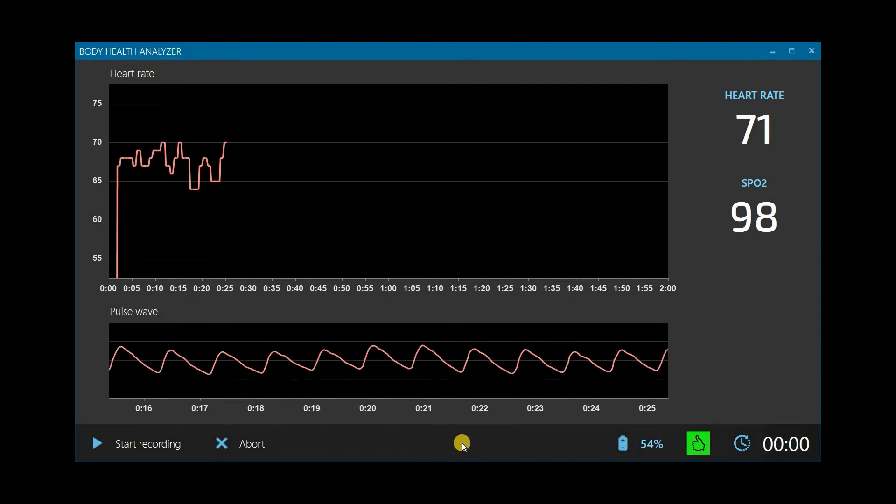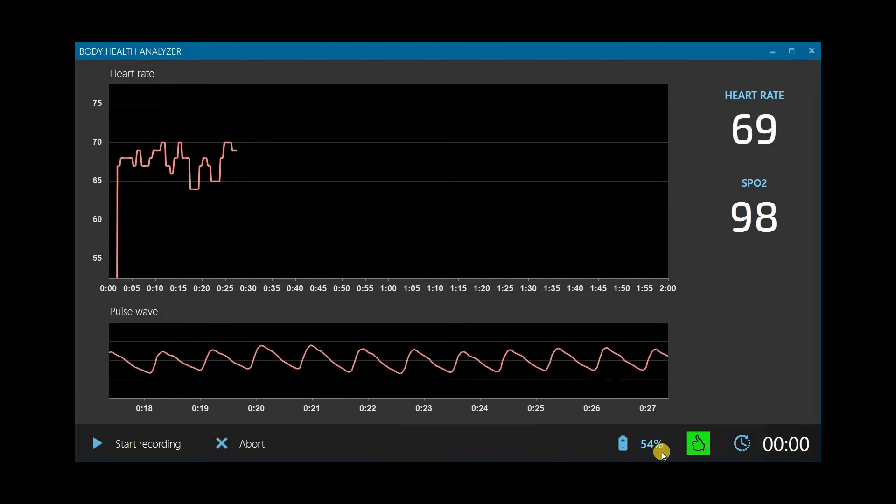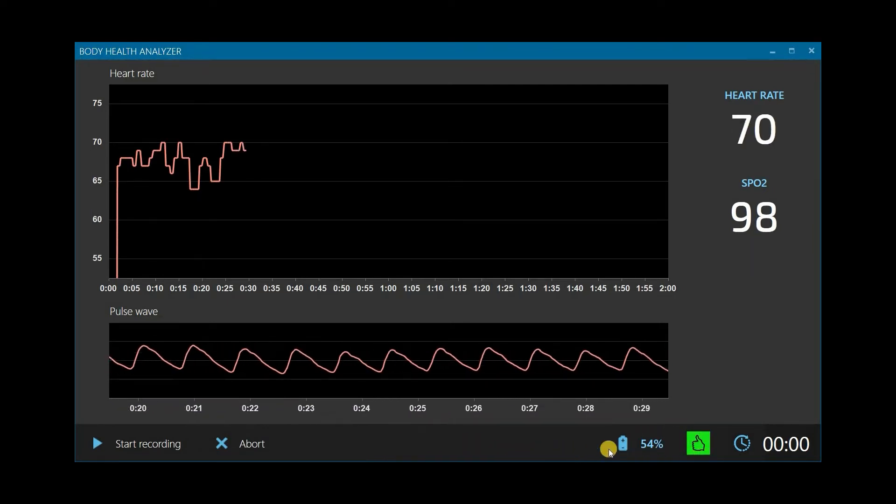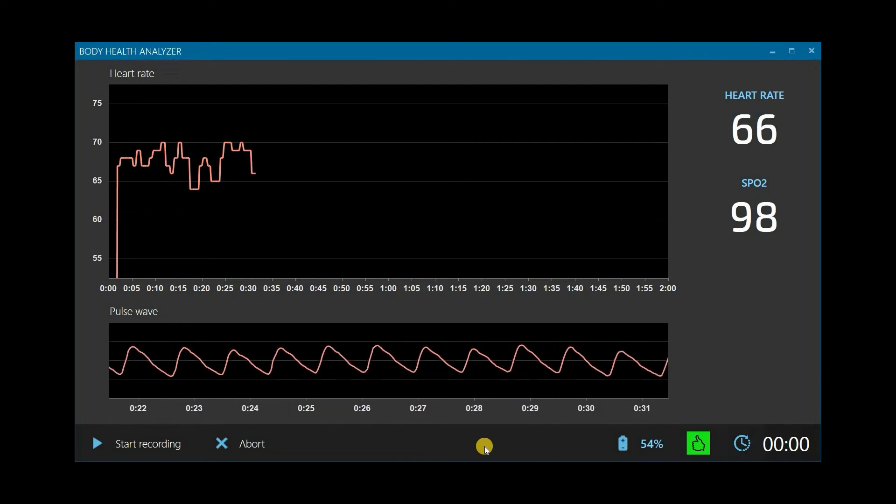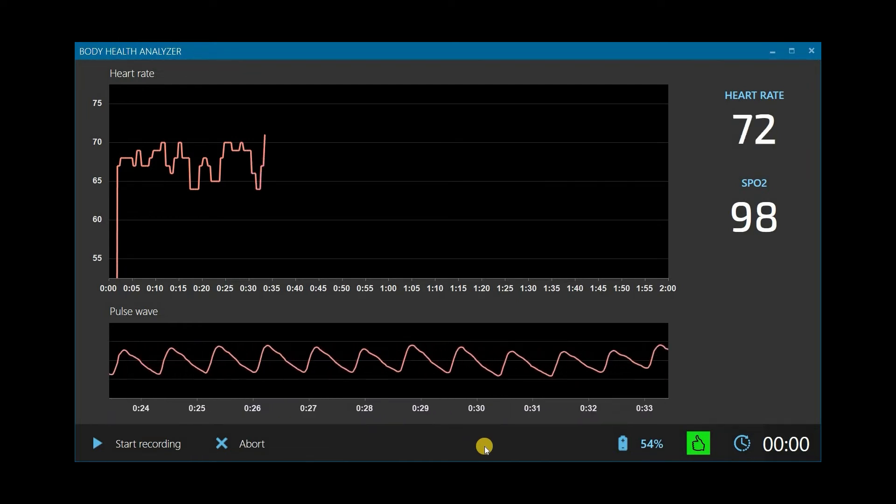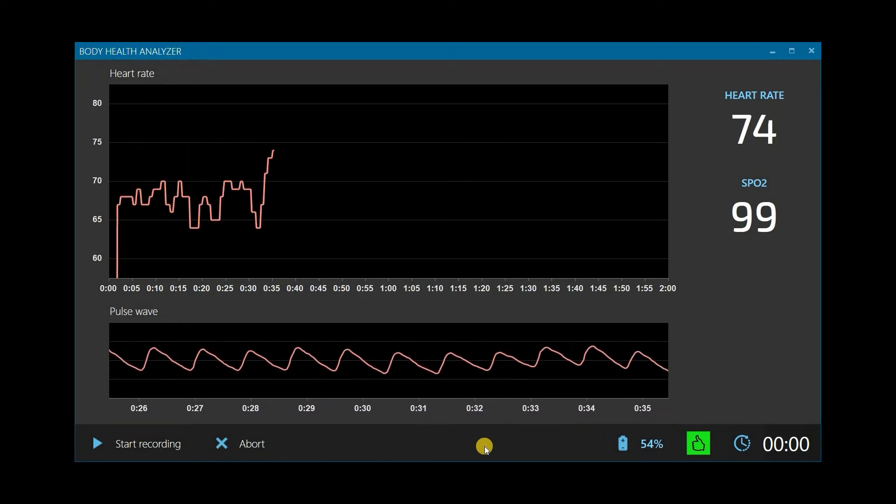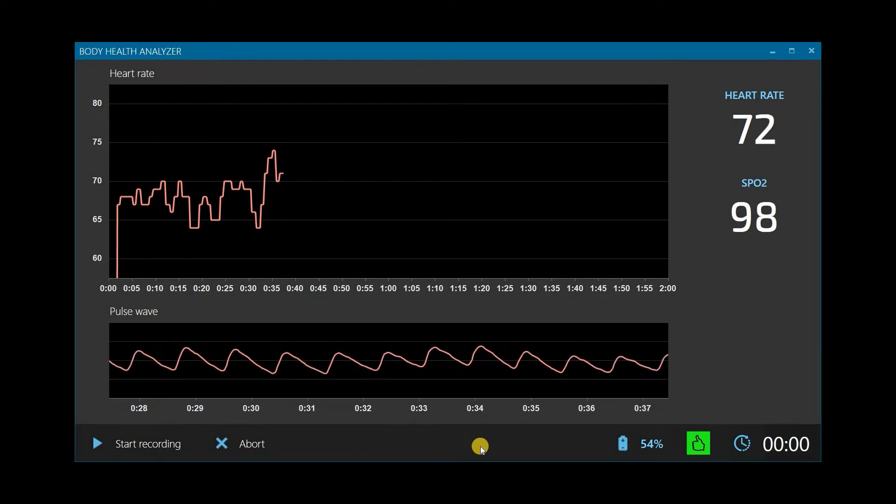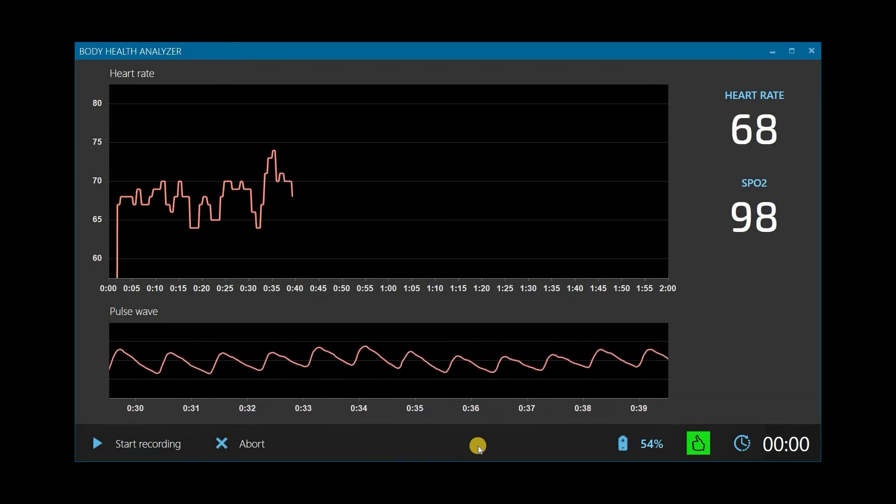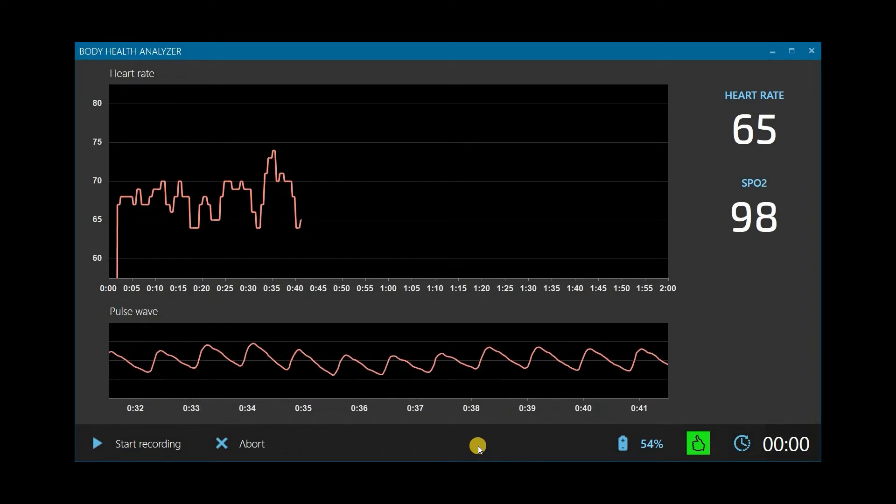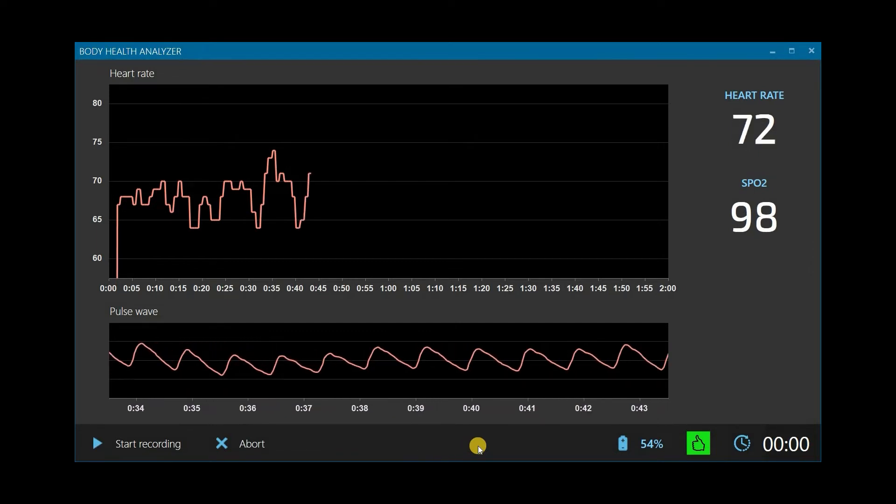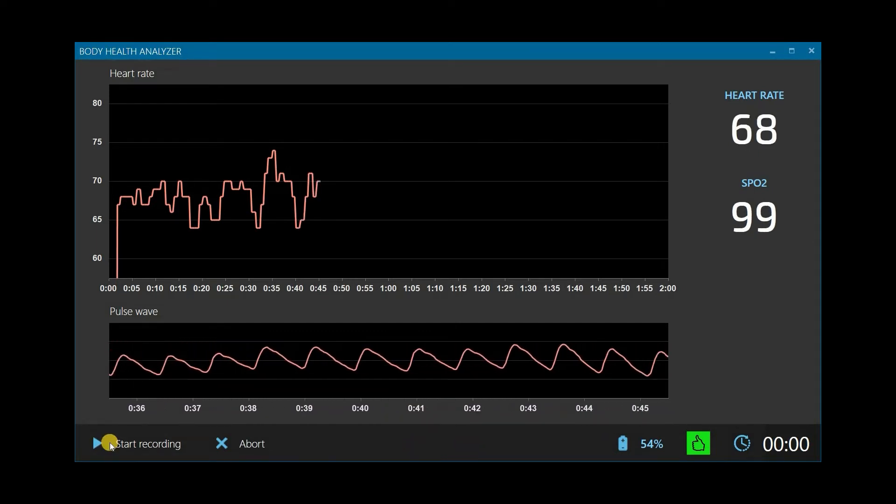The software automatically analyzes measured data and indicates its quality as a colored square. Green means the data is clean and good to record. Yellow means there are some minor disturbances happening, but it is still good to record. If it is red, there are too many disturbances in the recorded data, so the test should be aborted. Once you see that measured data is good, click Start Recording.